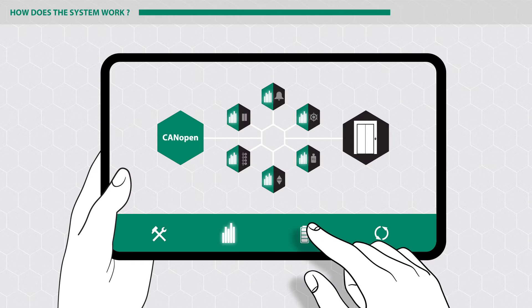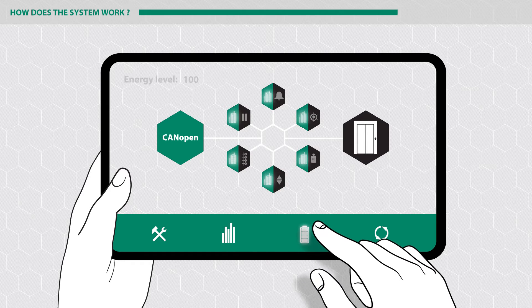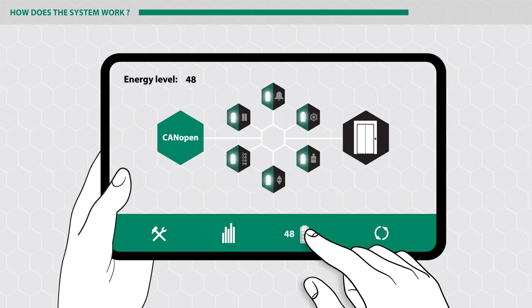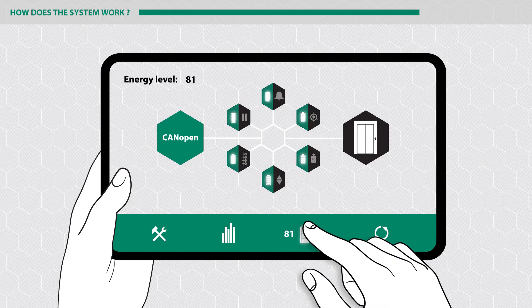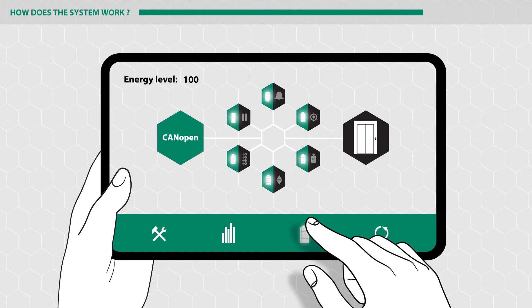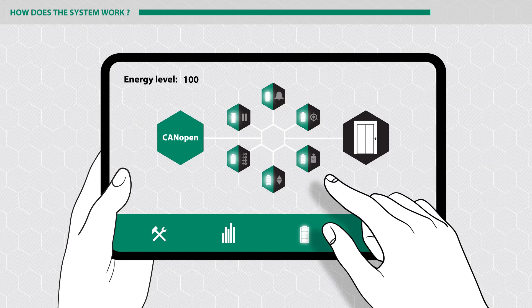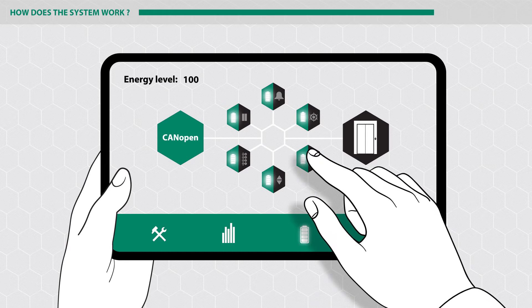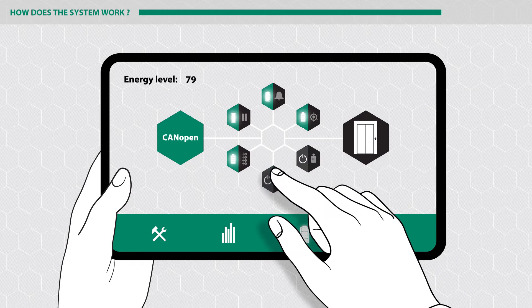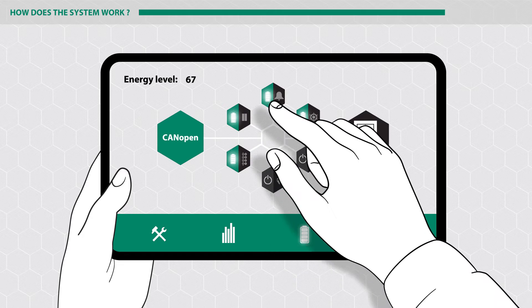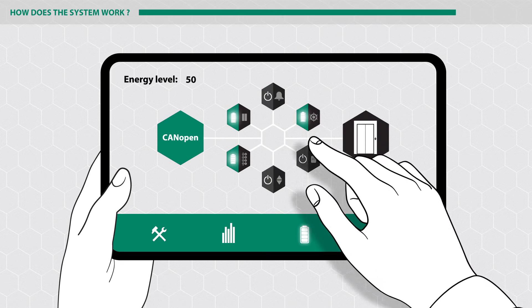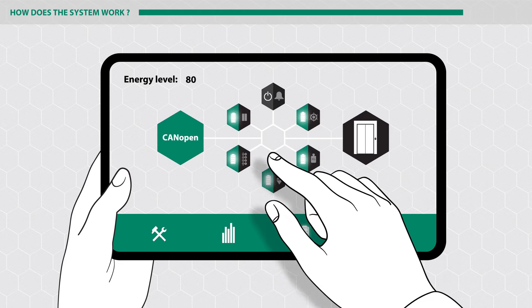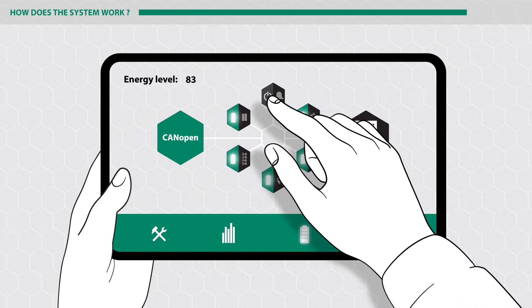The integrated energy management provides a method for continuous monitoring and for reducing energy consumption of elevators. By activating different standby modes in the components, the energy consumption of the elevator can be controlled as required. Thus, CANopenLift provides a uniform manufacturer-independent method for energy saving.